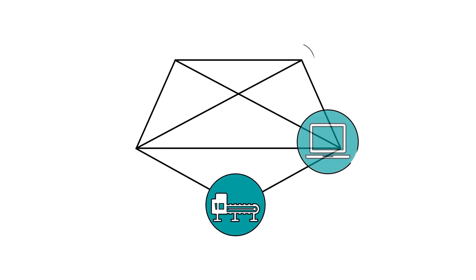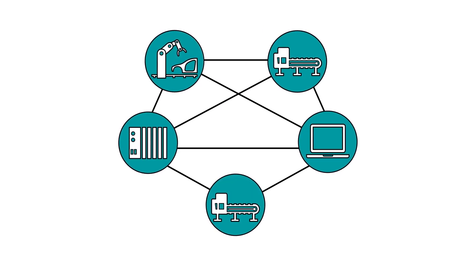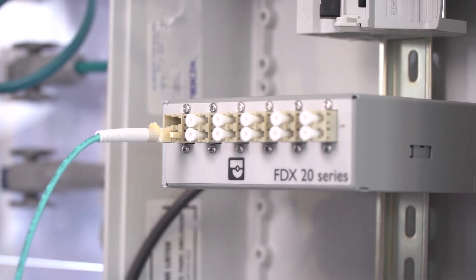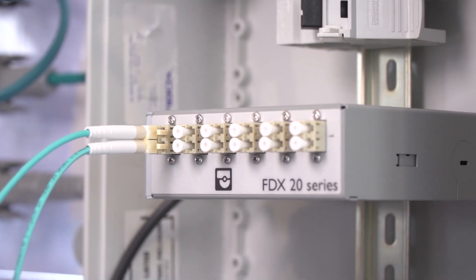The main purpose is to protect the long fiber optic cable runs. For example, when fiber is run to a remote location within a facility for purposes of monitoring system performance. By doing all the termination in the splice box, the long fiber run is protected. Once terminated, patch cables are then used to connect with equipment within the control room.